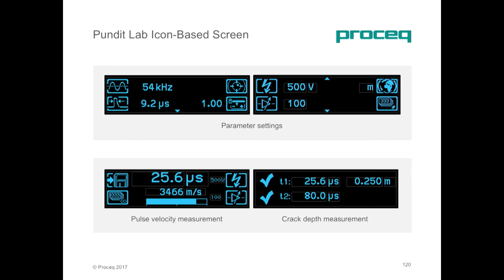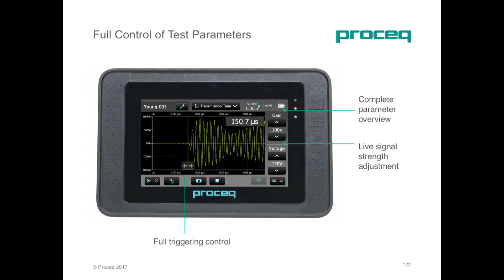The Pundit 200, as you can see, is a rugged IP54 device. It has a high-resolution Gorilla Glass touch screen, and it also supports pulse echo testing. So it's a very useful instrument to have on site. You have full control of the test parameters. It's something that's difficult to show on slides, but basically you can control all of your transmission settings directly during a measurement, and you get instant feedback on the touch screen. You can't underestimate this when you're working on site, to give you confidence in your test results.